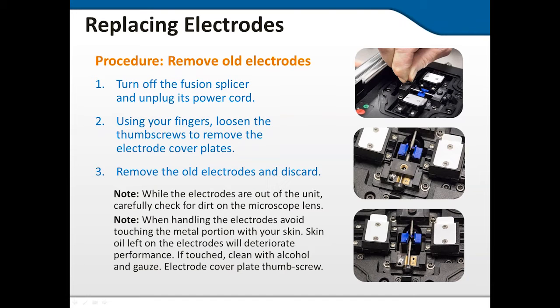So while the electrodes are out, carefully check for dirt on the microscope lenses. When handling the electrodes, avoid touching the metal portion with your skin. Skin oil left on the electrode will deteriorate performance. If touched, clean with alcohol and gauze. Electrode cover plate thumb screw.